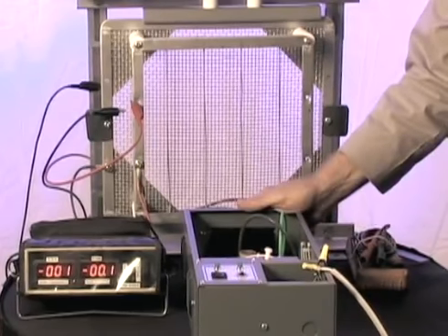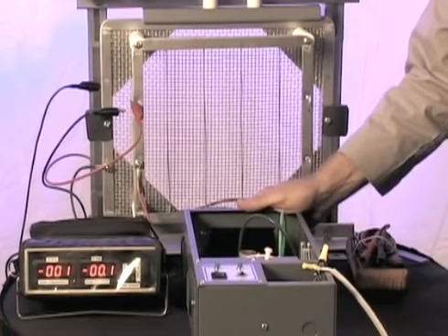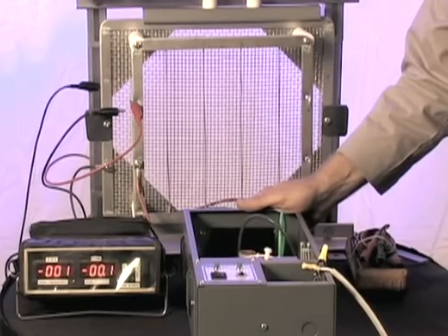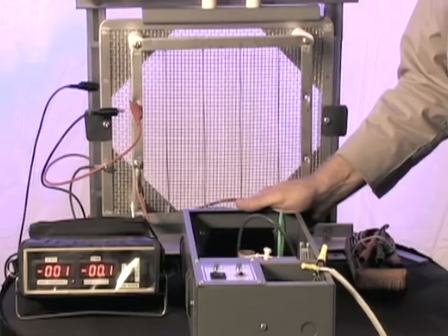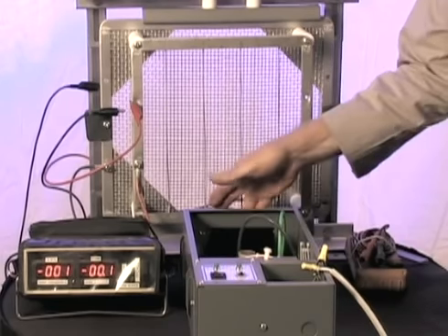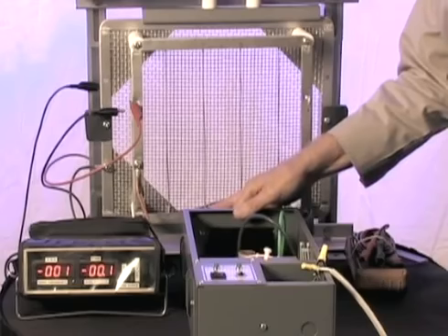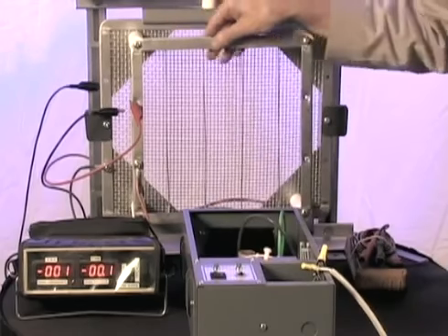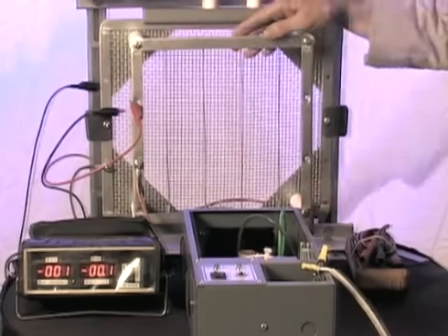If you've determined that there's a lot of contamination at the screen set, the next thing to do is to get a clean white rag, and I use 90% isopropyl alcohol. The alcohol content in it is so high that it will dissipate off the screens and the surrounding areas that you touch, and you won't have to worry about water remaining on any of the metal surfaces causing corrosion.